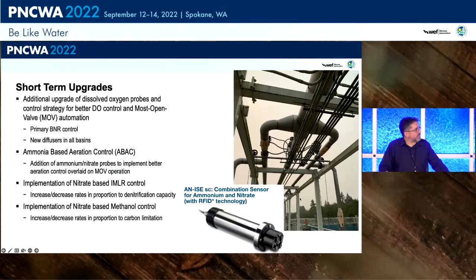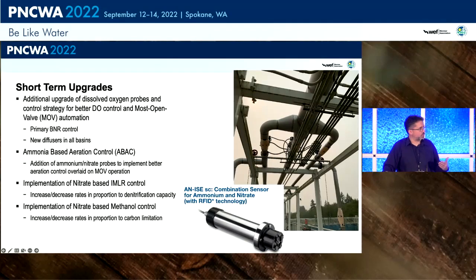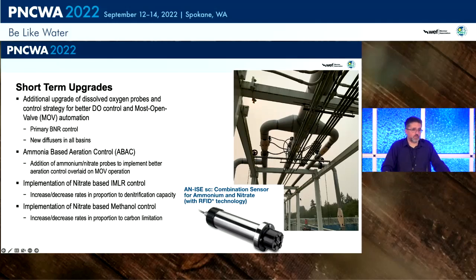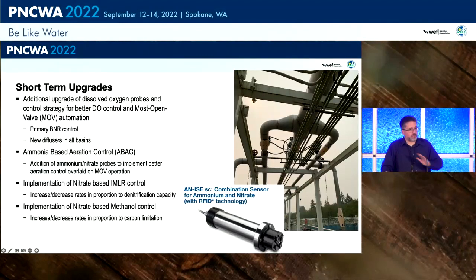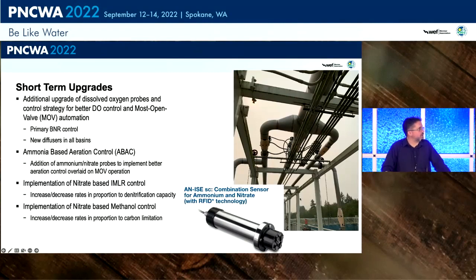On top of the MOV work, we added ABAC control using dual probes — some HACH ISE probes placed in the basins — to give us additional control points so we can control off ammonia and not just DO. We also implemented those probes to provide a secondary option for controlling the internal mixed liquor recirculation streams based on nitrate levels, to decide how best to utilize the anoxic zone. And we could also get control off methanol — up to this point the plant would essentially flatline methanol feed. Sometimes it's too much, sometimes not enough. We wanted another control variable to make better use of it.